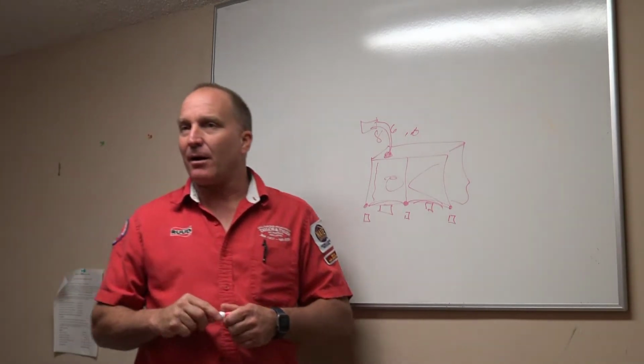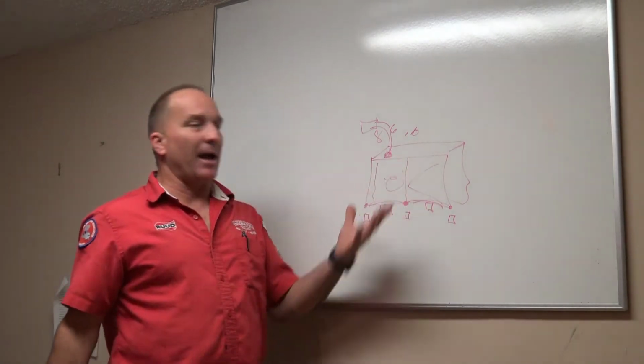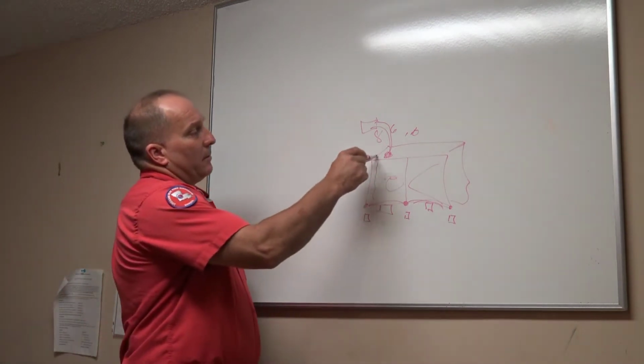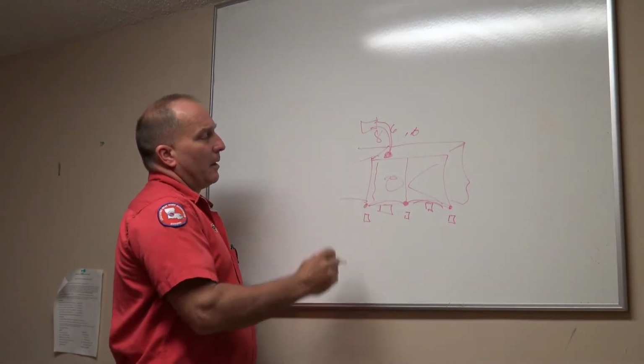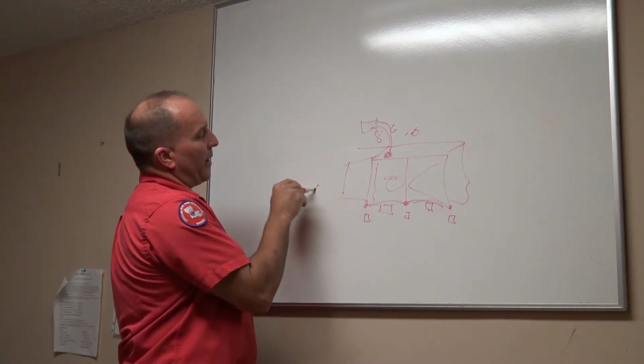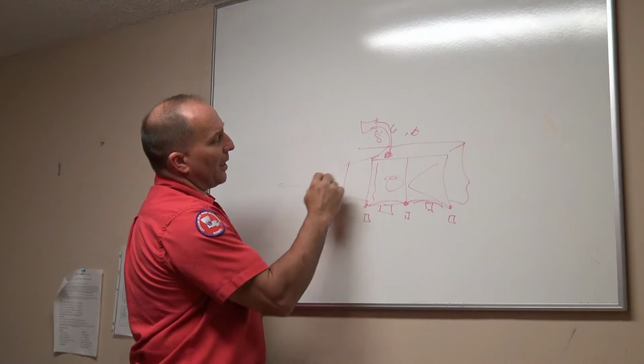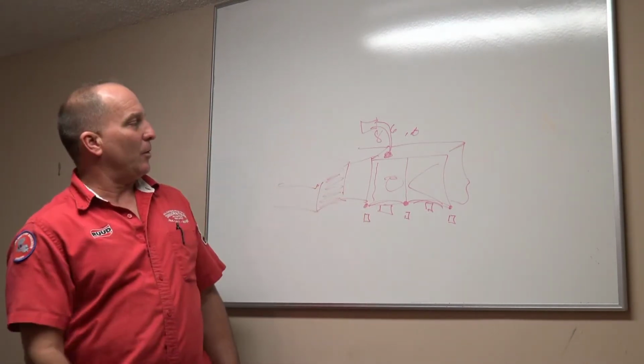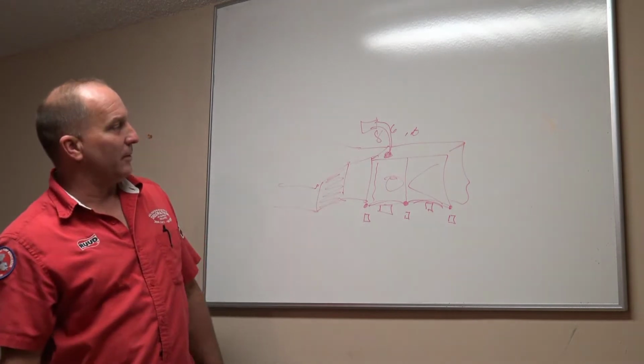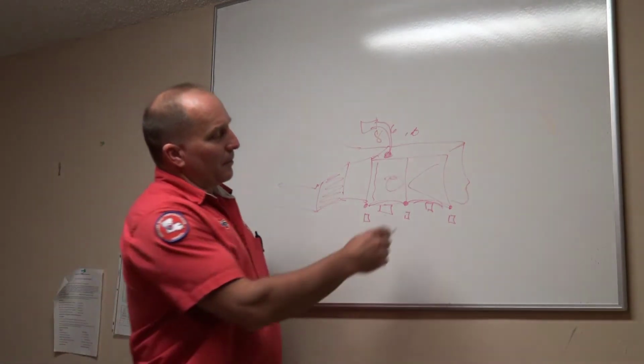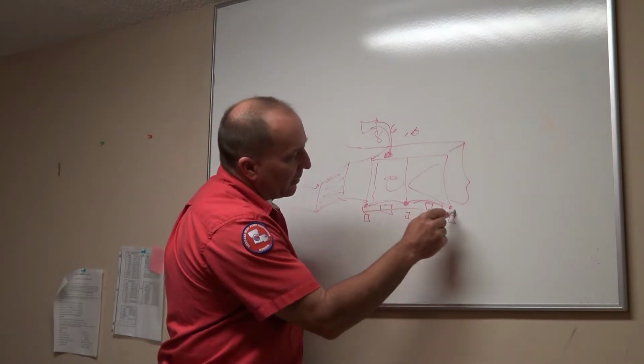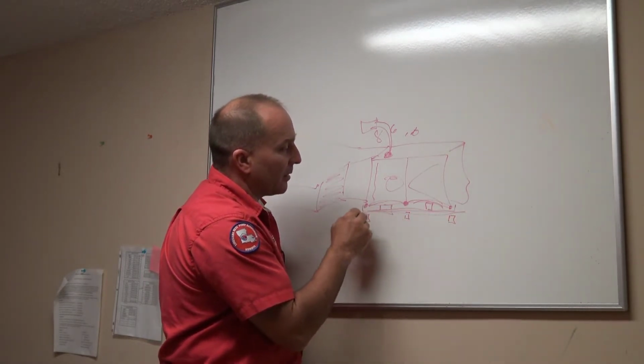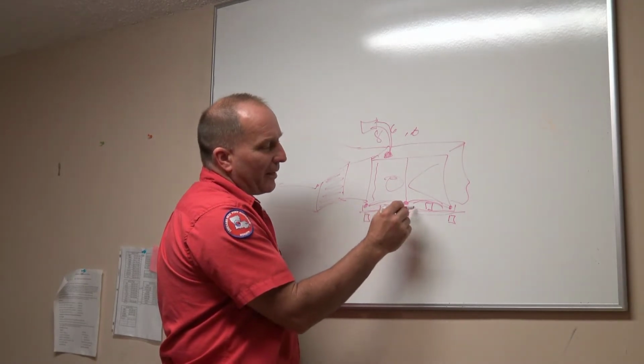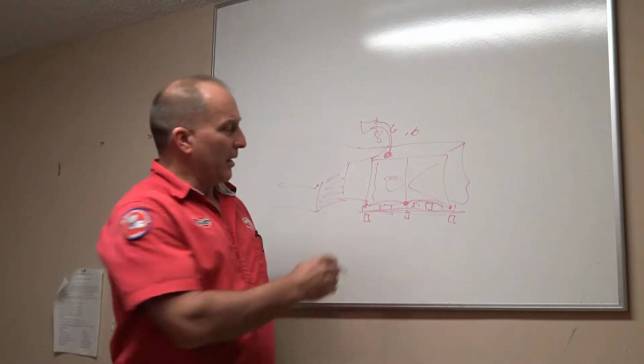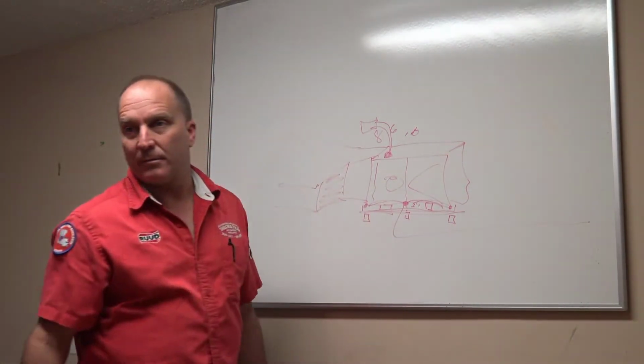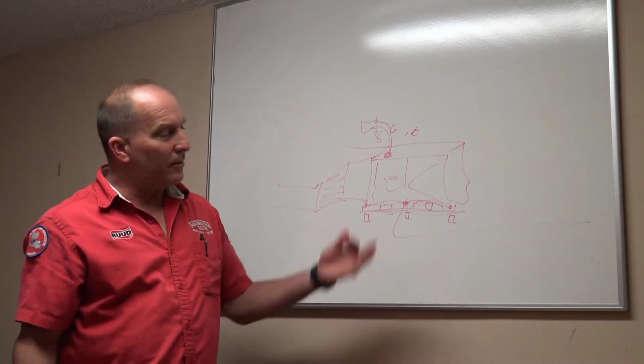What is the condition of the air handler? What is the condition of it? That's what I'm asking you. Look at it. Transition comes out from here, and then the plenum comes out this way. And then they got all this blocked off right here. I'm going, whoever installed this thing isn't working. They're stupid, okay? I look at my drain line, my drain pan sits underneath here, and it sits on top of plywood right here. And then my downflow from my drain line is 2 inches. And then it runs out here and runs 20 feet over that way. What's the condition of my air handler, guys?